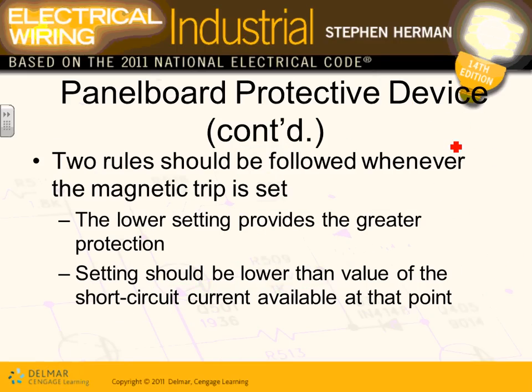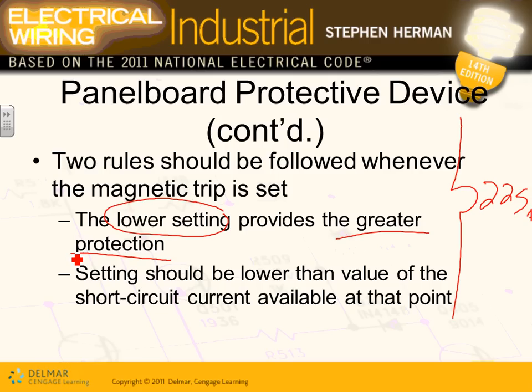Two rules should be followed whenever you set the magnetic trip. So when you put a circuit breaker like this, Adam, which is 225 amp, and you need to set up the adjustable circuit breaker, you guys, Matt, you did the short circuit study through SKM. When you set them up, here's the rule. I hope you guys will remember this one. The lower the settings, the greater the protection. The lower the setting of the circuit breaker, the greater the protection. The setting should be lower than the value of the short circuit current available at that point. You should be able to handle the short circuit at that point.